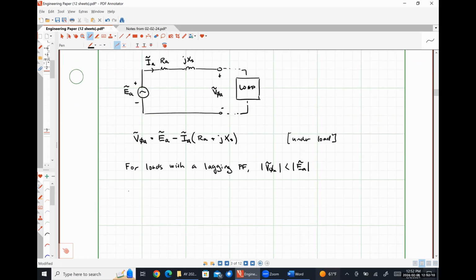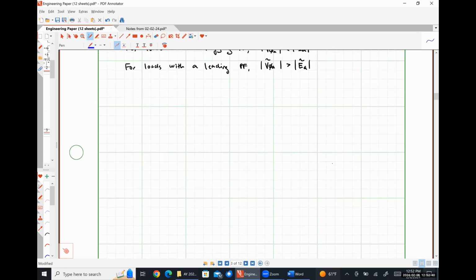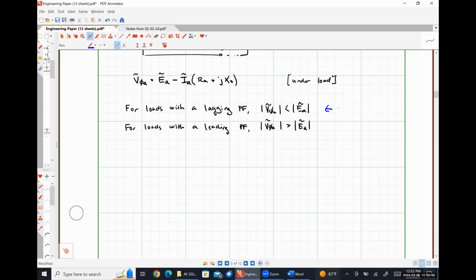Conversely, for loads with a leading power factor, the magnitude of our terminal voltage should be greater than our induced voltage. We typically call this condition—sorry, the screen scrolled on me—over excitation, and this condition under excitation.